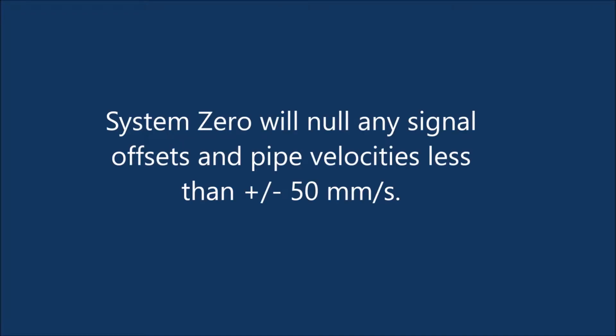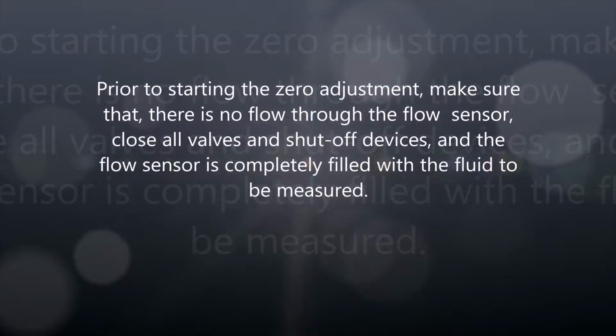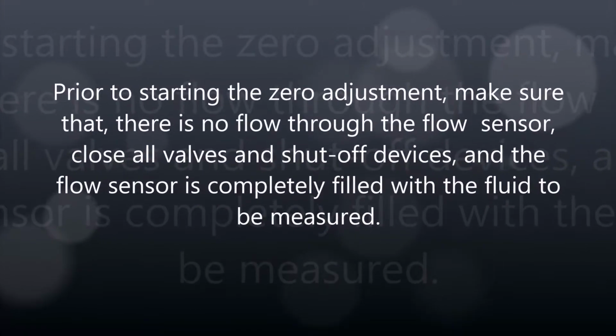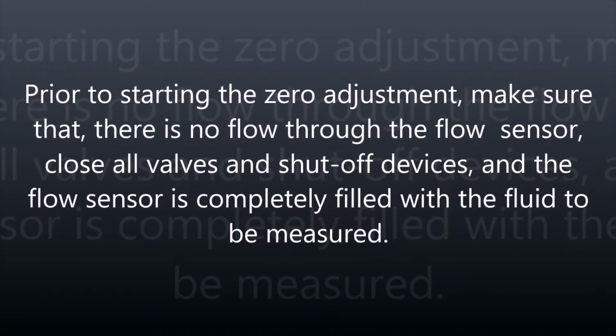System 0 will null any signal offsets and pipe velocities less than plus or minus 50 mm per second. Prior to starting the 0 adjustment, make sure that there is no flow through the flow sensor. Close all valves and shut off devices, and the flow sensor is completely filled with the fluid to be measured.